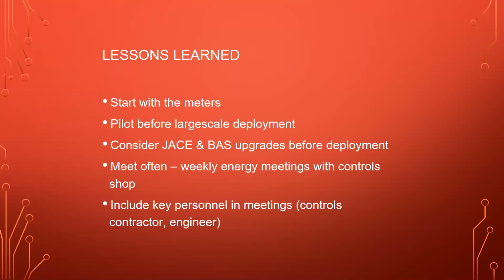As Elliot mentioned, we found it very helpful to do a pilot on a small scale. We had a 200,000 square foot building that we did a pilot on, and we had quite a few bugs to work out related to tagging and some equipment upgrades. We had a situation where we lost a whole bunch of programming because the JACE crashed - that's the JACE we were pulling data from - so we kind of had to start all over again. That brings me to my next point: if you are doing JACE or BAS upgrades, make sure it would be helpful to do those before you deploy your analytics software.